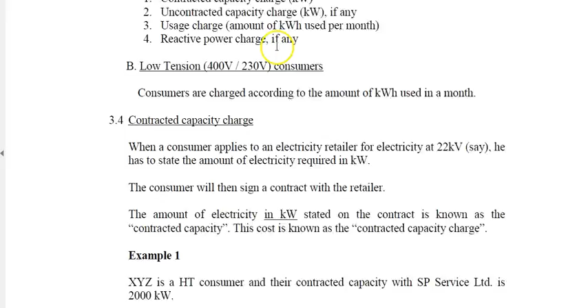Let's see an example. Company XYZ is a high voltage consumer, and the contracted capacity with SP Services Limited is 2000 kilowatt. But the maximum demand recorded for the first 3 months of the year are as follows: 1800 kilowatt for January, 2000 kilowatt for February, and finally 2100 kilowatt for March.